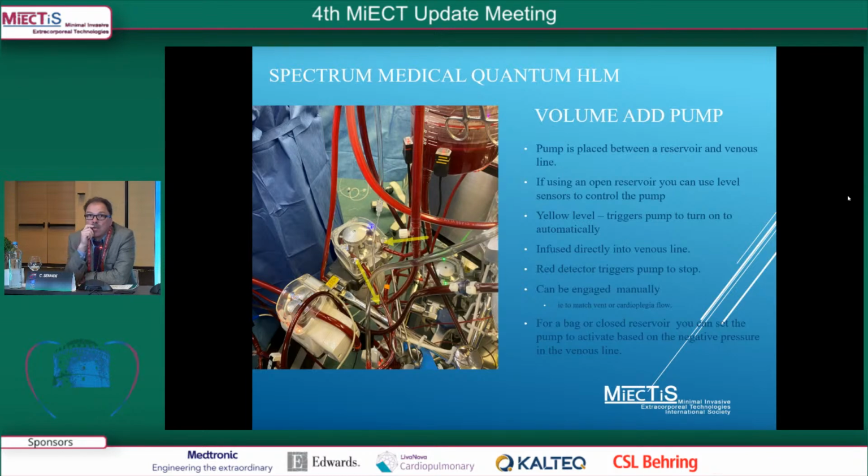We talked yesterday about working with our industrial partners, and we worked with Spectrum Medical for the Quantum heart-lung machine, and ran some of the first cases on mini bypass using Quantum. And one thing that we came up with was what we call the volume add pump, where any vented air will be sent into a cardiotomy reservoir.